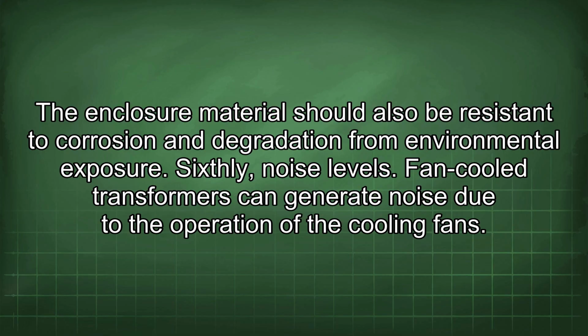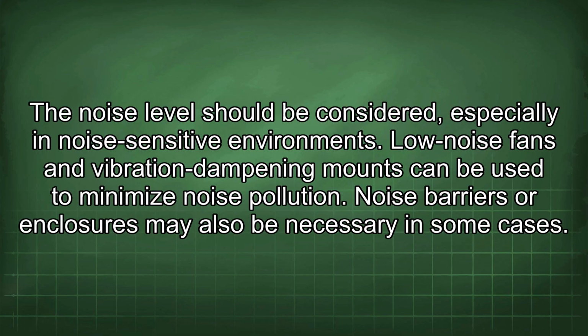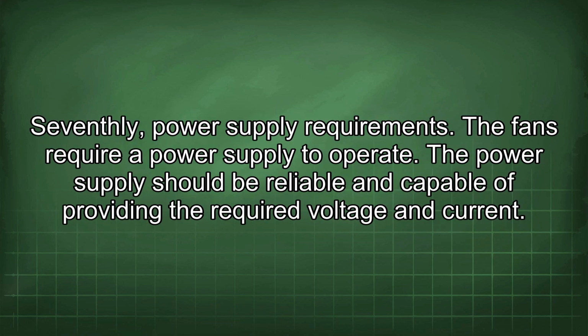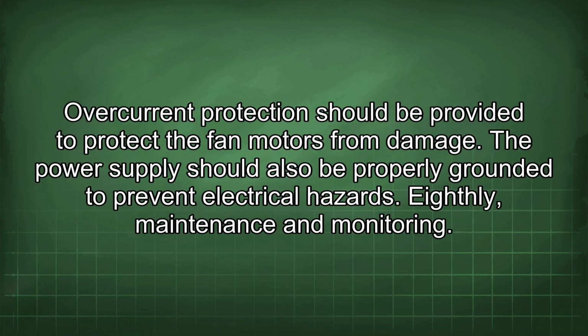Sixthly, noise levels. Fan-cooled transformers can generate noise due to the operation of the cooling fans. The noise level should be considered, especially in noise-sensitive environments. Low-noise fans and vibration dampening mounts can be used to minimize noise pollution. Noise barriers or enclosures may also be necessary in some cases. Seventhly, power supply requirements. The fans require a power supply to operate. The power supply should be reliable and capable of providing the required voltage and current. Overcurrent protection should be provided to protect the fan motors from damage. The power supply should also be properly grounded to prevent electrical hazards.